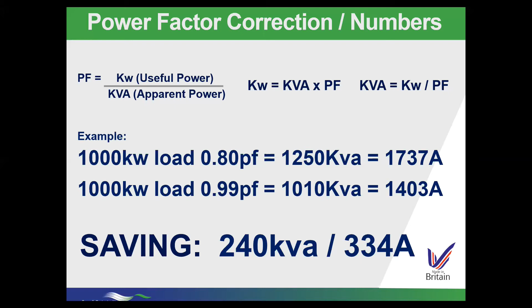So a lot of the benefits are in kilowatt hour losses, as I've just described, but also large commercial and some industrial premises will have a penalty called a reactive power charge or reactive surcharge because the power factor is low. And that's really because the network operator, the DNO, and I know you spoke to Electricity Northwest before, have to put in a bigger infrastructure for you if you're pulling more energy than you should be to do exactly the same task. So someone's got to pay for that, and there's normally a penalty, a reactive power charge, because that organization is pulling more power than it should do.